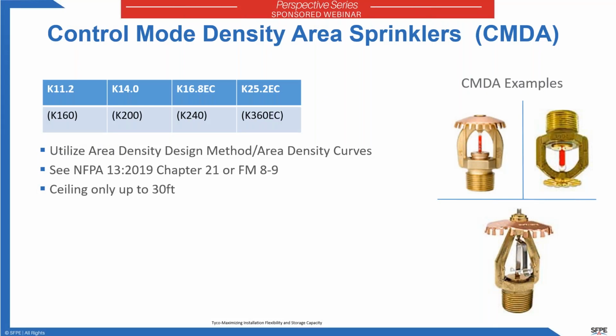For many, many years in the fire sprinkler industry, the only type of sprinkler that was essentially available was a control mode density area sprinkler, or CMDA. These are currently used in non-storage applications, in the occupancy type of protection schemes, and were the first sprinklers used for storage applications. Typically, they're based on an area and a density. In the sprinkler world, density is the gallons per minute per square foot discharged through a sprinkler. So if a sprinkler was protecting 100 square feet, and you're discharging 20 gallons a minute, that's about a 0.2 density. Just a quick example for you there.